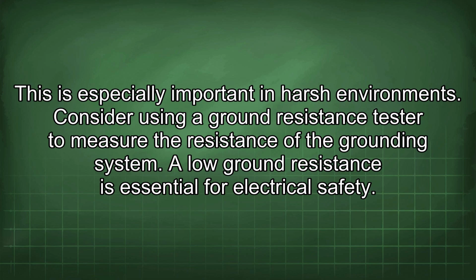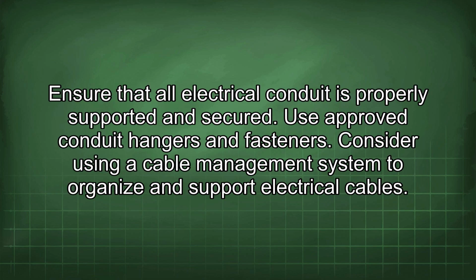Consider using a ground resistance tester to measure the resistance of the grounding system. A low ground resistance is essential for electrical safety. Ensure that all electrical conduit is properly supported and secured. Use approved conduit hangers and fasteners.